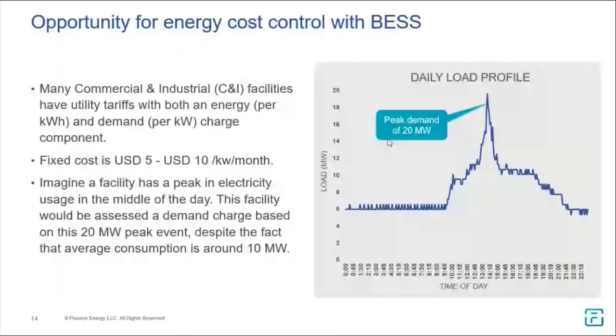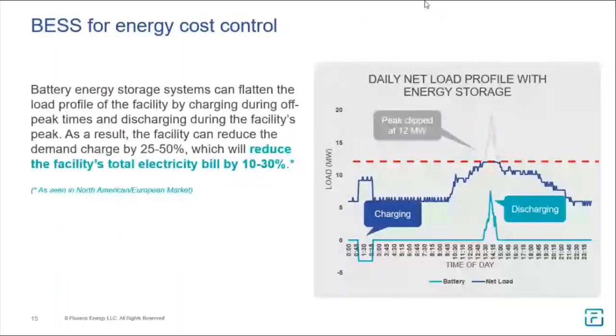With the battery and software, you can deploy it to basically shave off that peak. The moment your load hits above 12 megawatts and goes up to 20, the battery is sized to cater to that load. So when you get your connection, you don't have to go for the full 20 megawatts. You can get a connection for 12 megawatts and save on the fixed cost for the remaining 8 that's being served by the battery.